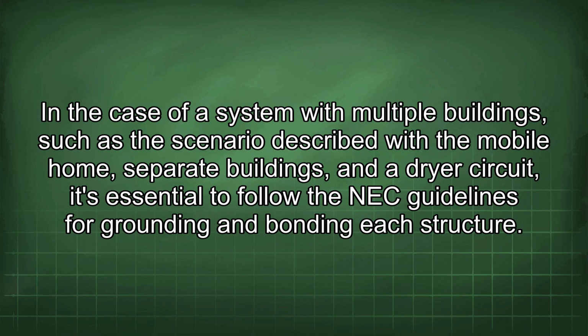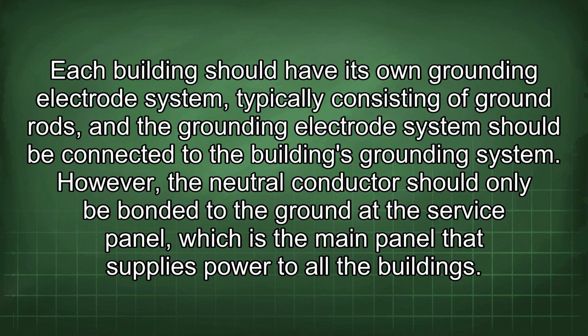In the case of a system with multiple buildings, such as the scenario described with the mobile home, separate buildings, and a dryer circuit, it's essential to follow the NEC guidelines for grounding and bonding each structure. Each building should have its own grounding electrode system, typically consisting of ground rods, and the grounding electrode system should be connected to the building's grounding system. However, the neutral conductor should only be bonded to the ground at the service panel, which is the main panel that supplies power to all the buildings.